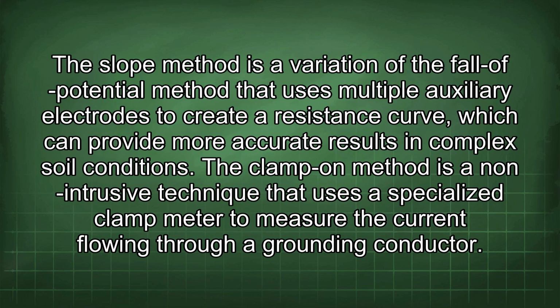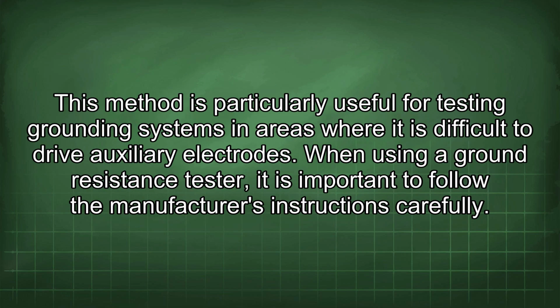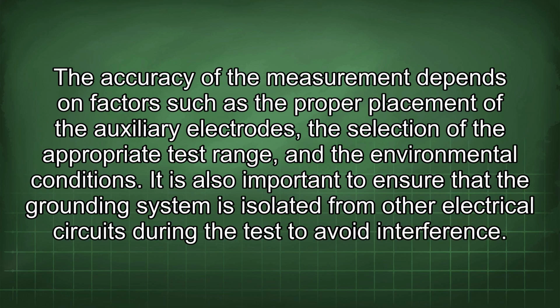The slope method is a variation of the fall-of-potential method that uses multiple auxiliary electrodes to create a resistance curve, which can provide more accurate results in complex soil conditions. The clamp-on method is a non-intrusive technique that uses a specialized clamp meter to measure the current flowing through a grounding conductor. This method is particularly useful for testing grounding systems in areas where it is difficult to drive auxiliary electrodes. When using a ground resistance tester, it is important to follow the manufacturer's instructions carefully. The accuracy of the measurement depends on factors such as the proper placement of the auxiliary electrodes, the selection of the appropriate test range, and the environmental conditions.